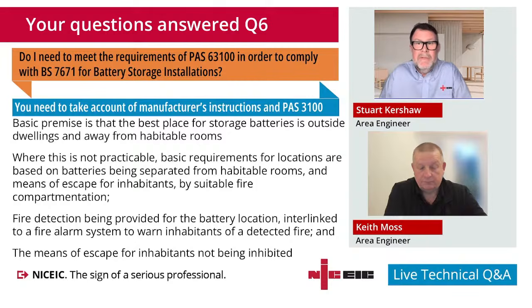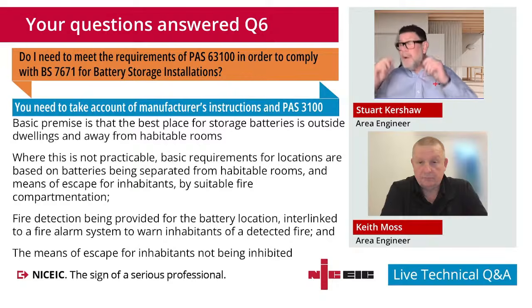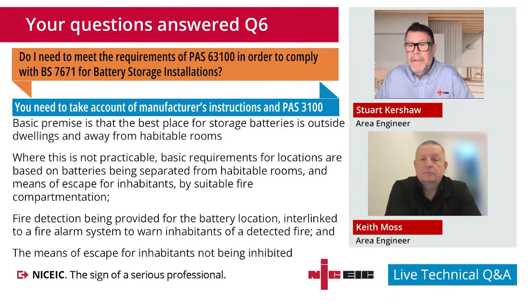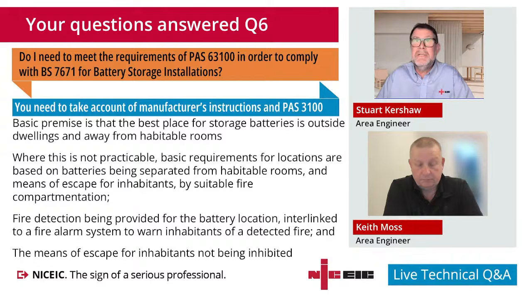And most of these electrical energy storage systems are suitably rated for external influences, IP67 ratings etc, so they can be installed outside externally. If we do have to install them internally, I've got a battery in my own garage, but it's on an external wall, mounted on some fire rated board, and there's an interconnected linked smoke detector compliant with BS 5839 Part 6 in that vicinity as well. So it's taking suitable precautions, but it is advised against in the PAS document.